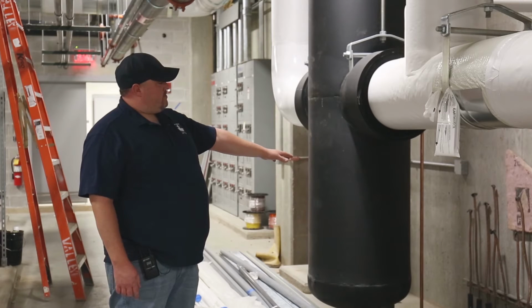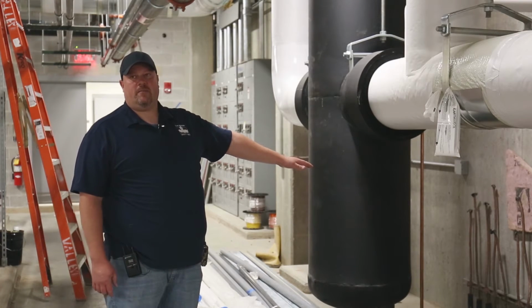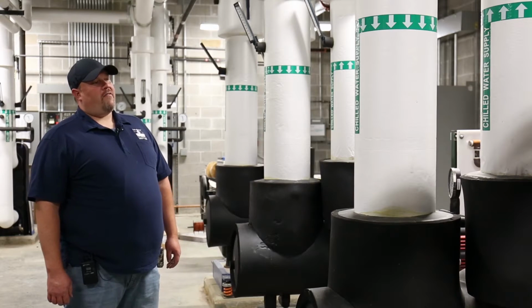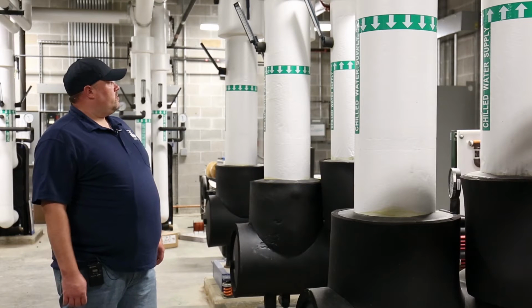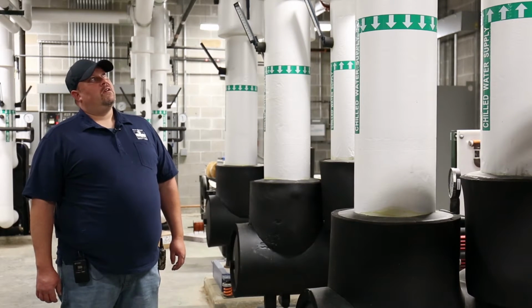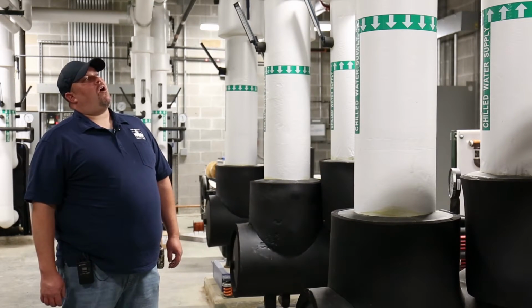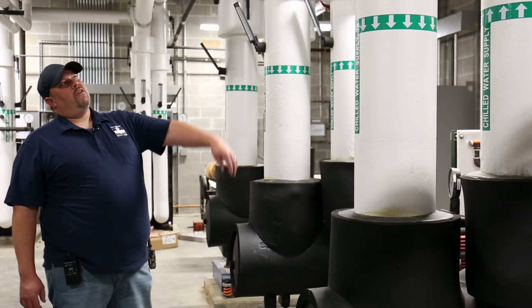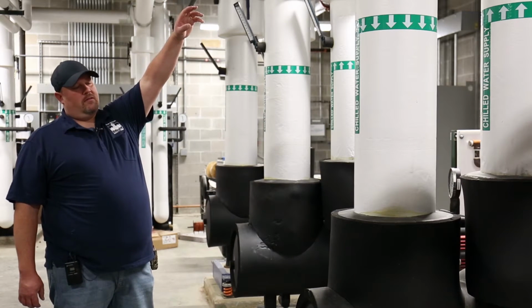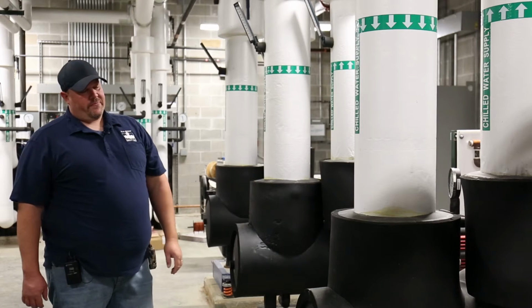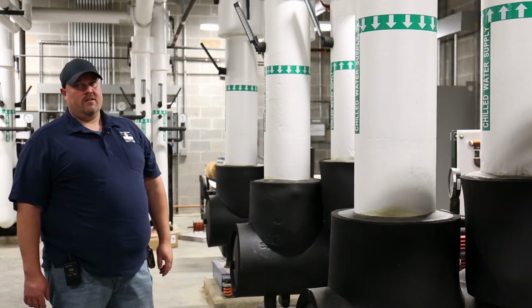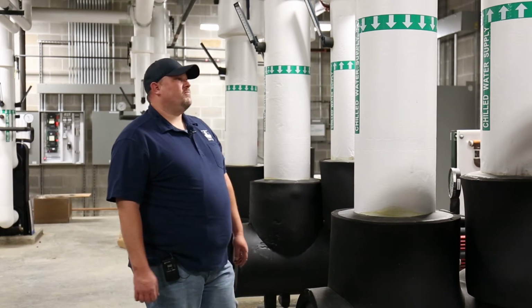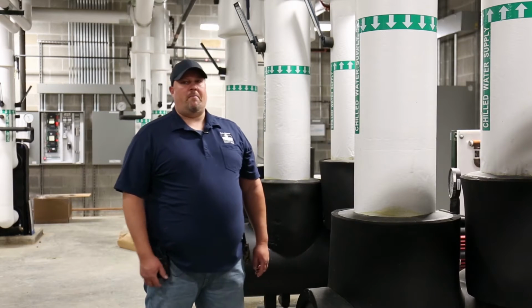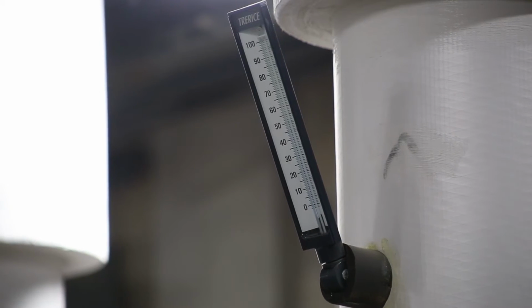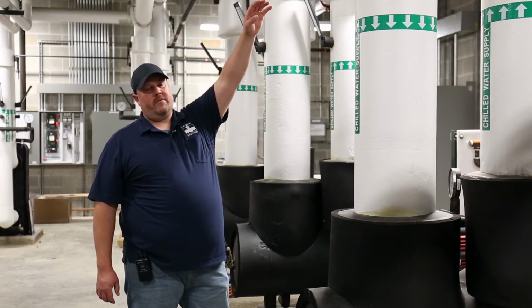And here we have a trap primer assembly that is yet to be installed. Here we have our chilled water pumps. Each pump is installed with an automatic flow control and a suction diffuser. As you see on these pumps, there are no triple duty valves for balancing. They're all controlled by these automatic flow controls.